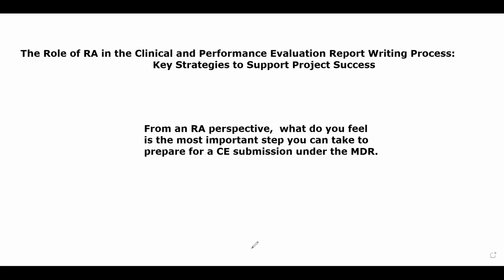If I were to choose one, it's the regulatory strategy, because out of that flows supporting the decision on what your regulatory strategy is. Our key answers to key questions say: what is our data sufficiency? What does our IFU look like? What are our claims? What are the clinical benefits that will be identified? And what are the clinical claims being made that require clinical data to back them up? What are our safety and performance objectives?